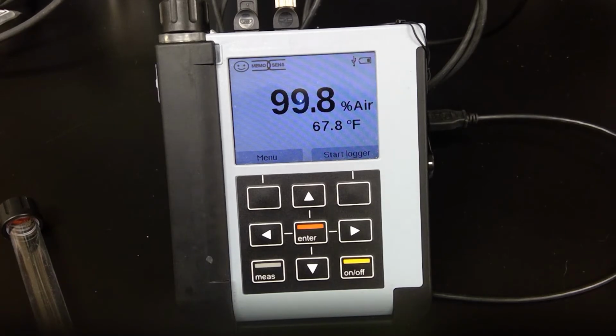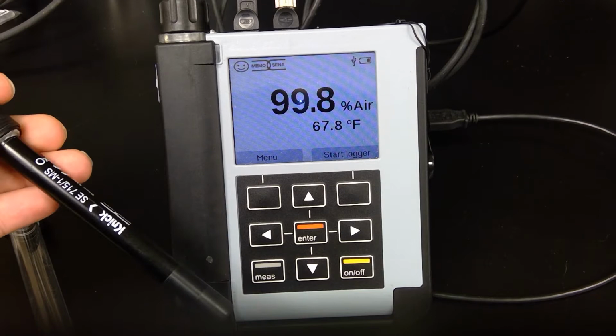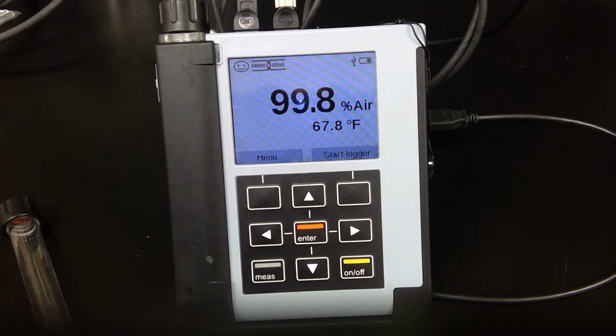If you recall, we did a video on how to change the membrane cap on an SE715. Now, in this video, what we're going to do is show how to do a basic air calibration for applications that are not in pressurized vessels or pipes. So this would apply to anything where a DO probe, an SE715 amperometric Clark cell sensor, is going to be used in an immersion style situation or ambient air pressure type applications.